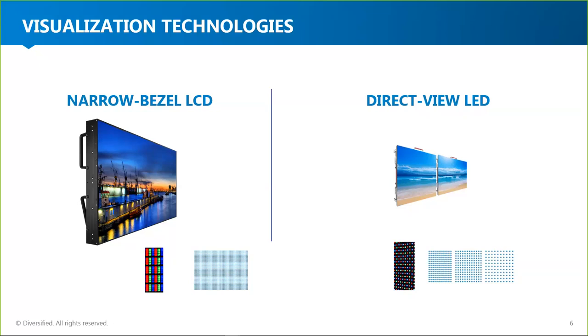You want to keep that. The life of an LCD is really interesting too, because it depends on how you have the brightness and the calibration set. If you take the brightness down a few notches, and you have the ability to do that because you don't have a lot of ambient light in your room, then you'll get a lot longer life out of it because it produces less heat. And heat is really the killer for LCDs in many ways. Heat comes not only from the technology that creates the display image, but also from the power supplies and things like that.